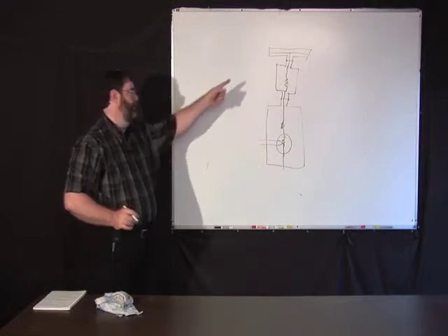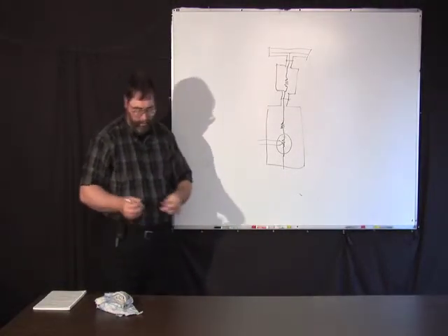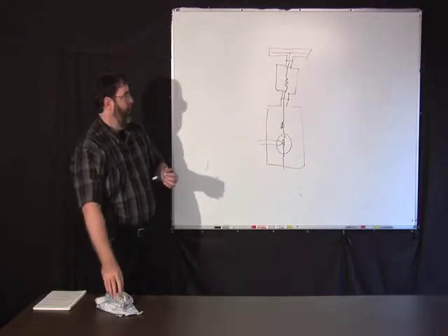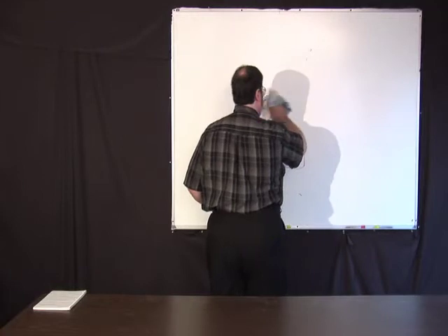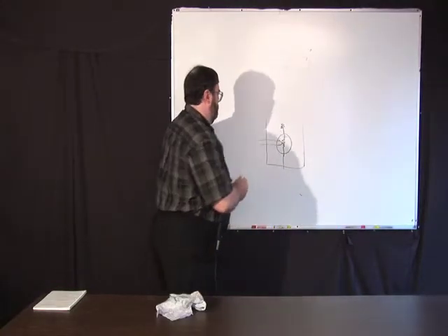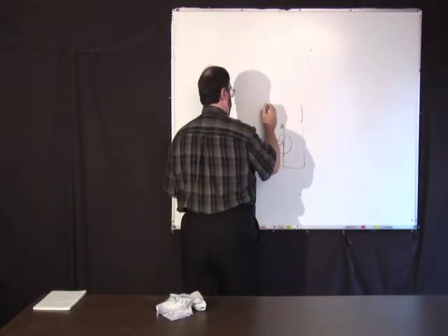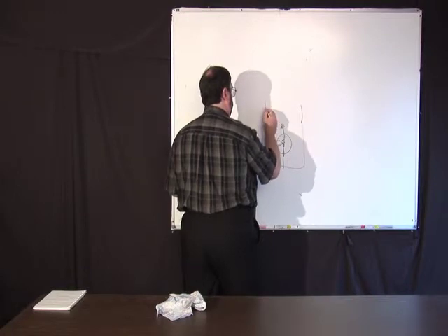To do the calibration, you have some DC standard and AC voltage put in there maybe, just to make it go faster, or you might do something else. But what generally happens with the RF ones, because of transmission line effects, they'll generally build in some sort of T.